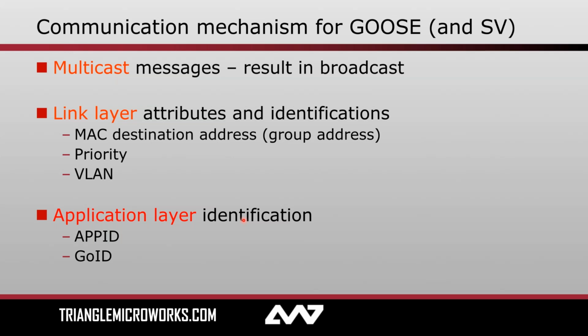There are a couple of link layer attributes that are used to identify a particular GOOSE message that can be used as tools in your tool chest. The first is the MAC destination address. This is just an alphanumeric string that identifies not so much the traditional destination, not a one-to-one destination address like we would have in TCP/IP communications, but maybe you could think of it as a group address. Additionally, we have priority and VLAN that we can set, if we're choosing to use this in our switches in order to prioritize certain messages through some sort of intelligent switch, or if we're using virtual networks or a software-defined network.